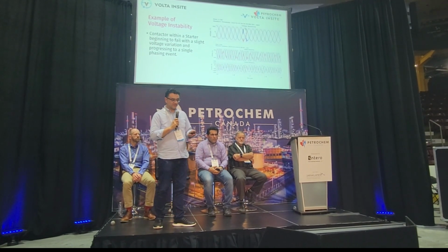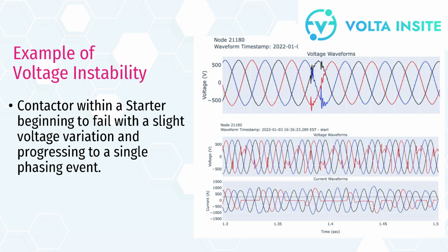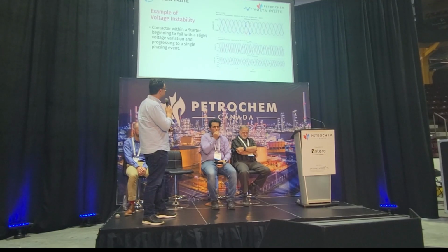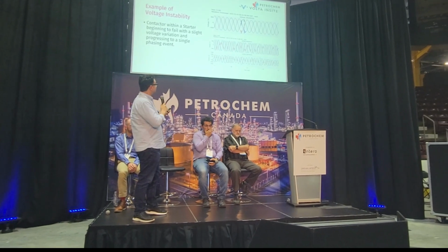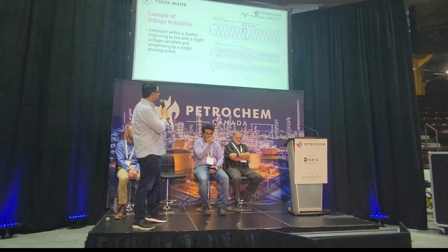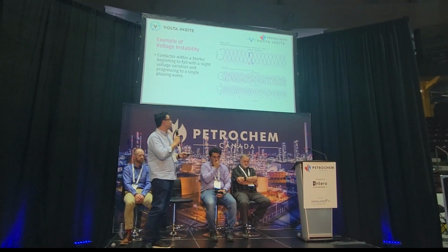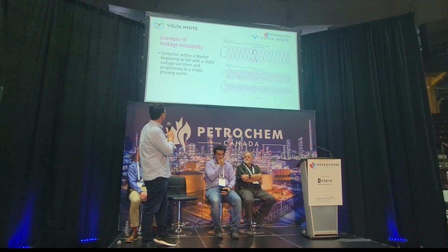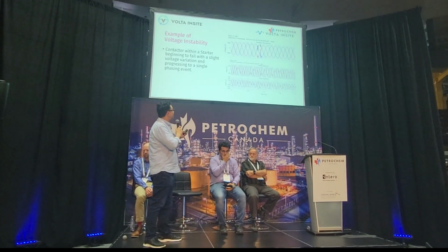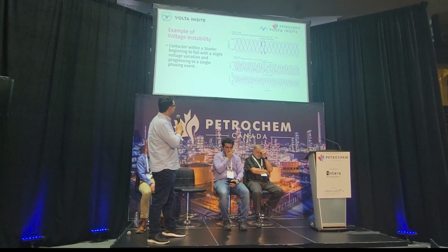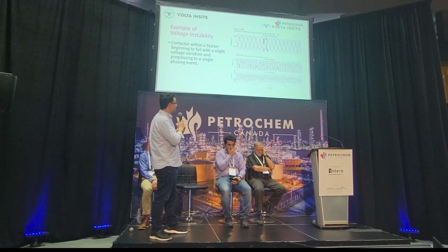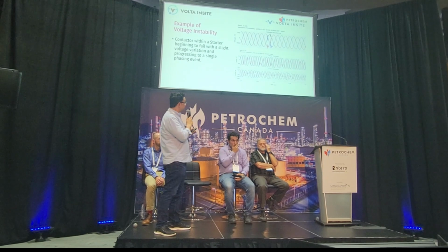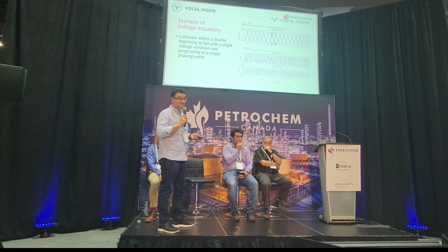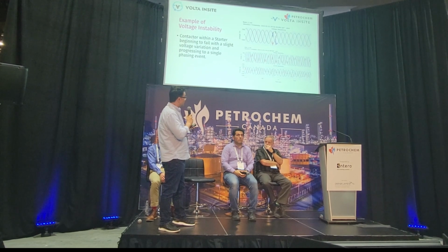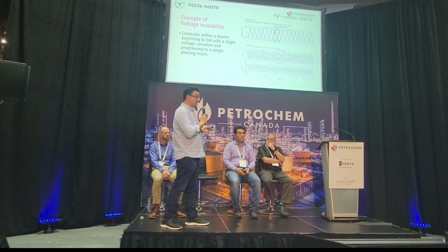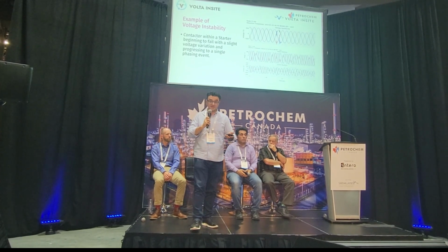Example of voltage instability. This is within your own distribution system at the facility level. So this is an example of a contactor starting to go bad on a motor. I think this specifically was a starter. Yes, it's in the writing. And you'll notice at the beginning of the day at around 6 a.m. we start detecting these voltage anomalies. By mid to end of day, we start having single phasing events. And if those events go for long enough periods of time, you will actually single phase the motor and ultimately have a catastrophic event.